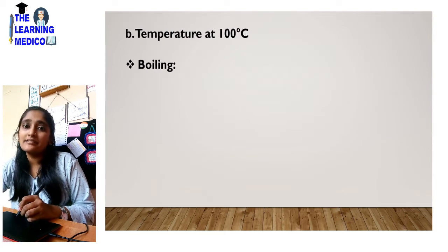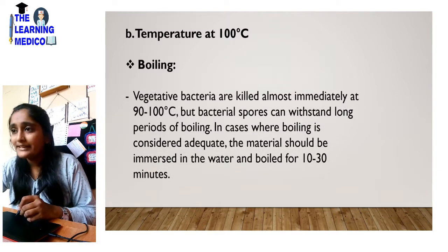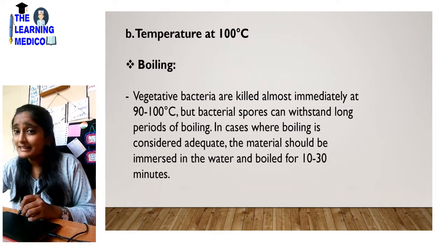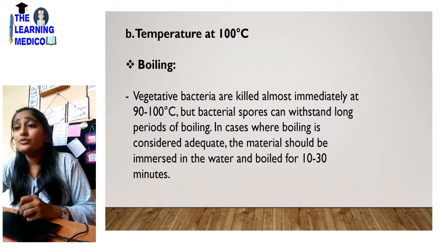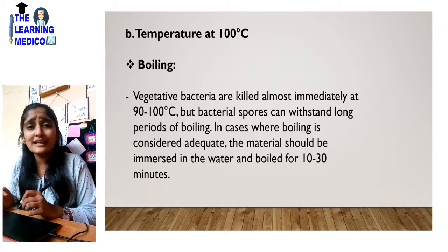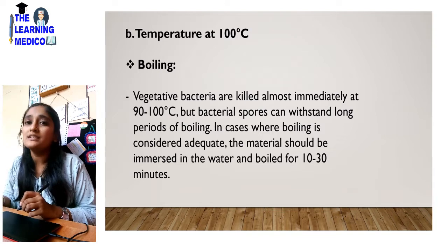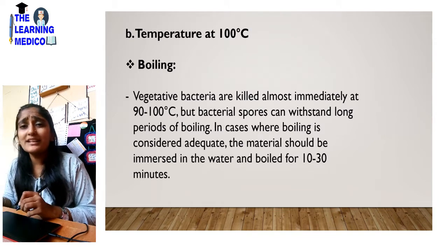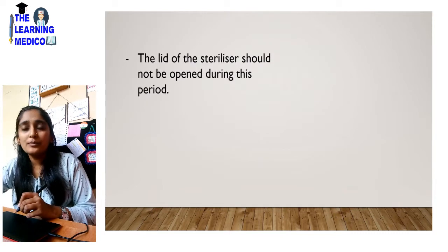Next is the temperature at 100 degrees Celsius, which is the boiling point. Vegetative bacteria are killed almost immediately at 90 to 100 degrees, but bacterial spores can withstand long periods of boiling. In cases where boiling is considered adequate, the instruments should be immersed in water and boiled for 10 to 30 minutes. The lid of the sterilizer should not be opened during this period.